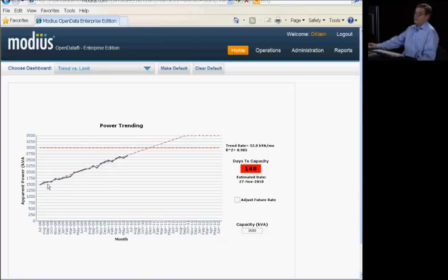And based on this historic data, we're able to fit a line which shows us its overall trend, growing power consumption over time. And from this line, we can then project forward when we're likely to run out of capacity at this location. And based on this calculation, you can see that we've been able to calculate that there's probably about 150 days of remaining capacity at this location until it needs to invest in either creating more capacity or shifting load to other locations.